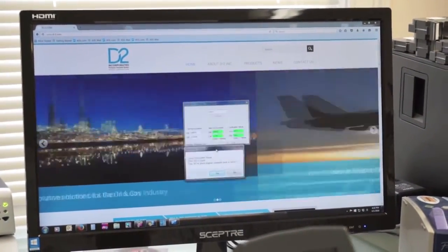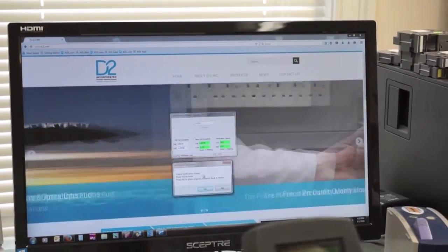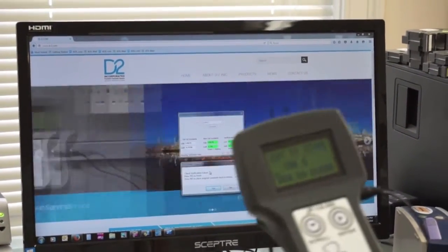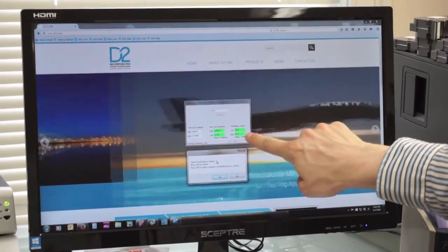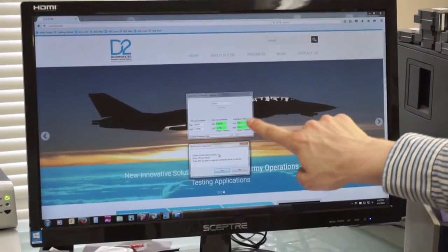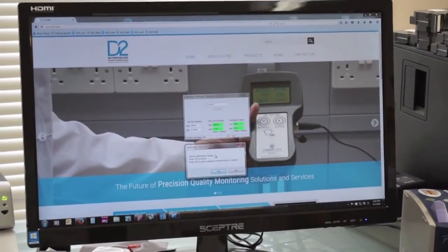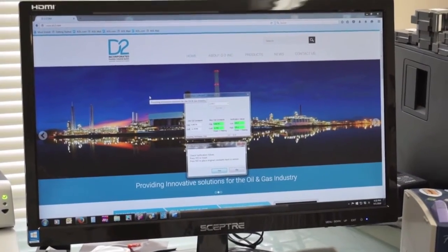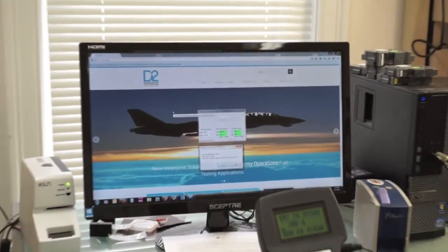And then here it says, check verification values, press yes to finish, press no to place original contents back into the sensor. So here what you want to do is check to make sure all of the values showing on this screen are in green. If that's the case, then the program has tested the new values and accepted them as accurate, and you want to save them into the sensor because your sensor is now calibrated with new values.